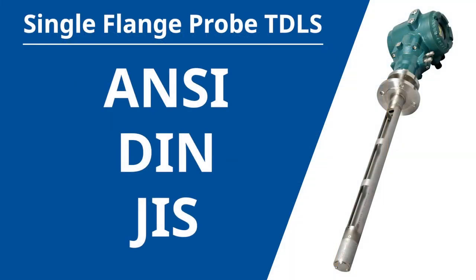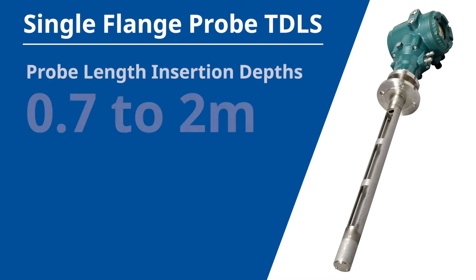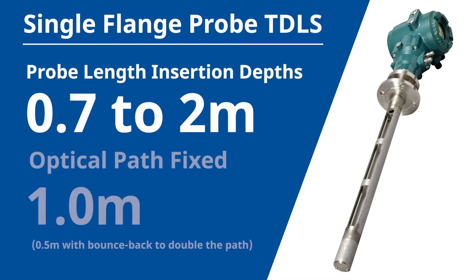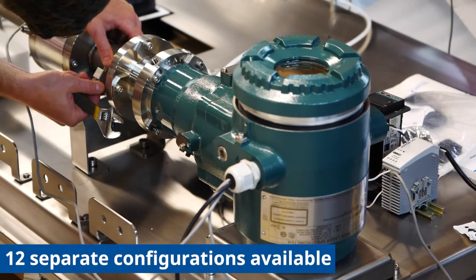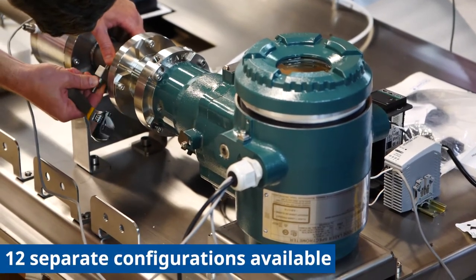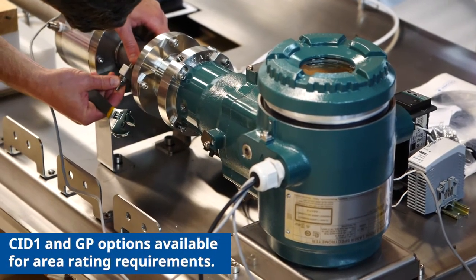The single flange probe TDLS was built to accommodate a variety of standard ANSI, DIN, and JIS process flanges. ANSI flanges start at 2 inch 150 pound and go up through 4 inch 150 pound. Contact us if you have any alternative flange needs like 300 pound flanges. The probe lengths have variable insertion depths from 0.7 to 2 meters. The optical path is fixed at 1 meter — half a meter with bounce back to double the path — and all that changes is the length from the flange to the beginning of the purge interface. Keep in mind which orientation you would like the display and head when ordering, as there are 12 separate configurations available. We also have separate Class 1 Division 1 and general purpose options available for area rating requirements.